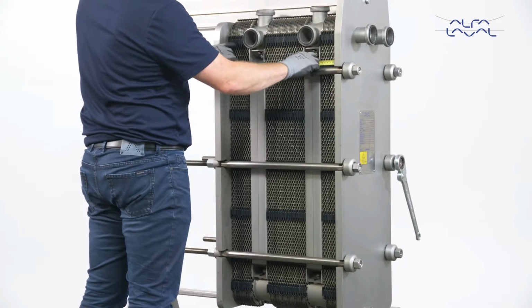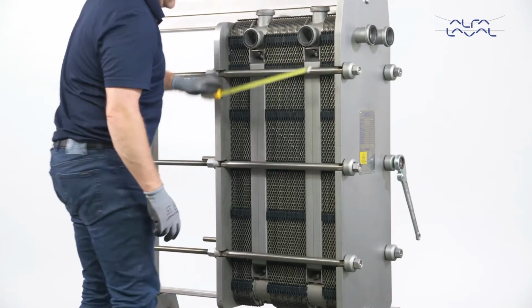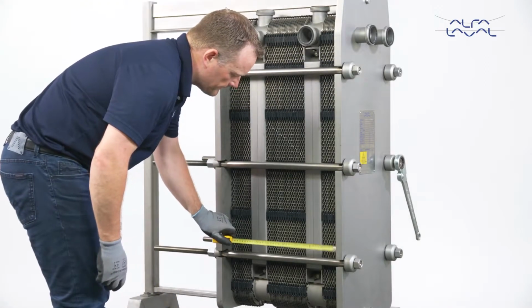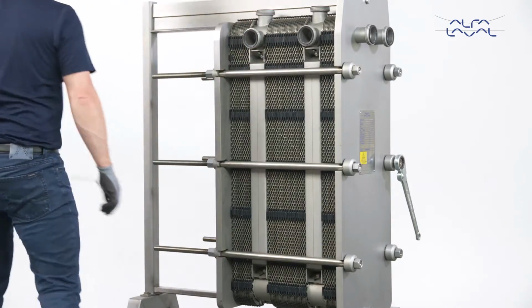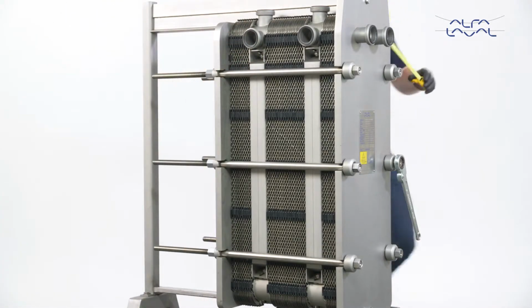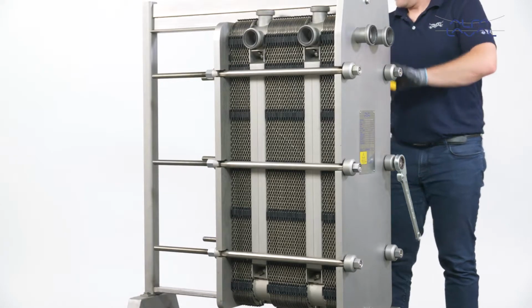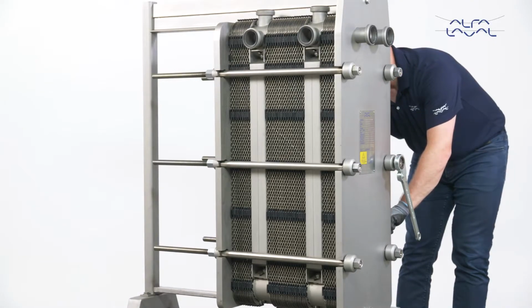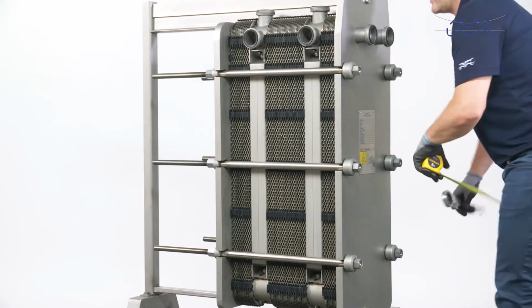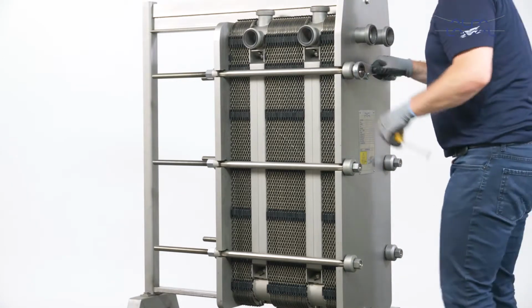Continue tightening until the A measurement has been reached. Do not over-tighten the heat exchanger. The maximum amount that the unit may be tightened is equal to the A measurement minus 0.5% of the total. Over-tightening will lead to plate damage and crushing of the gaskets.